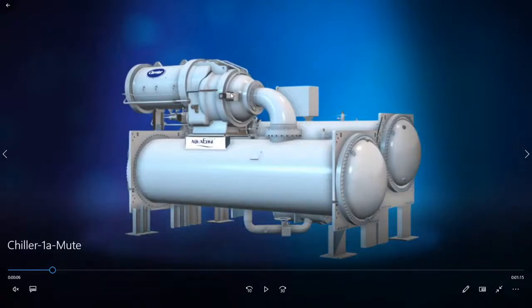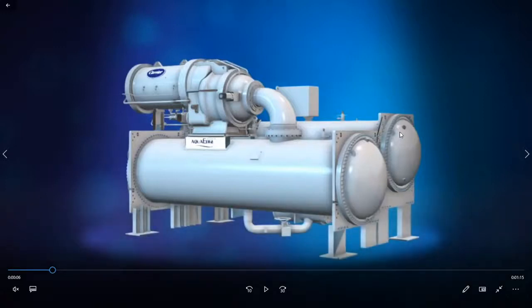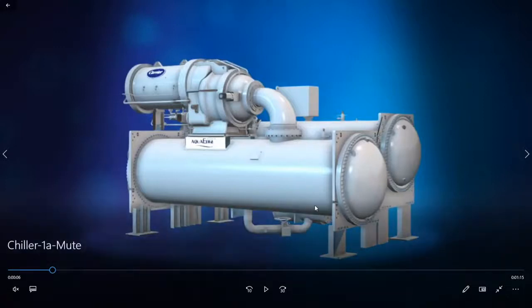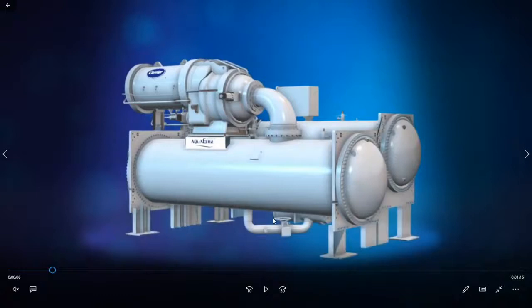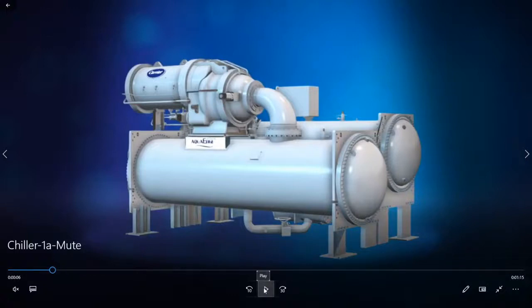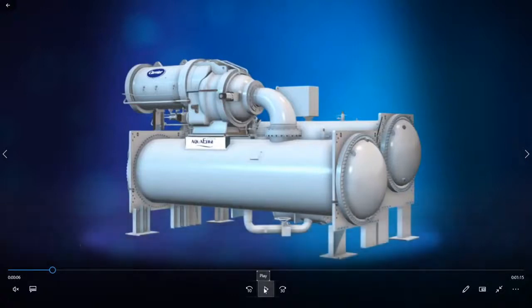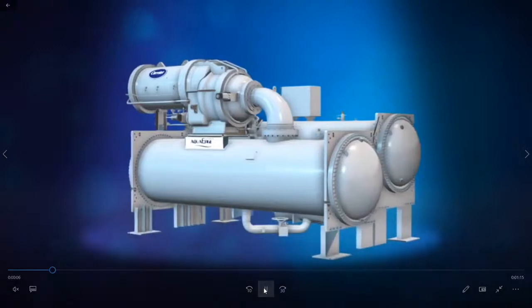And then from the compressor, the compressed vapor will go into the condenser, so that other vessel, which also is a shell and tube heat exchanger, would be the condenser, and in between there will be the expansion valve and other valves for various purposes, for safety and other requirements. So we have a view of the chiller, and you will see the other side as well.